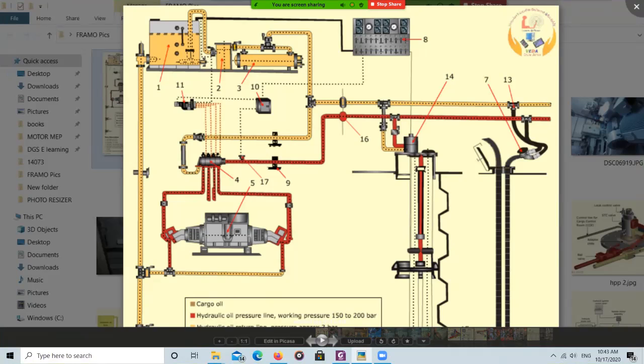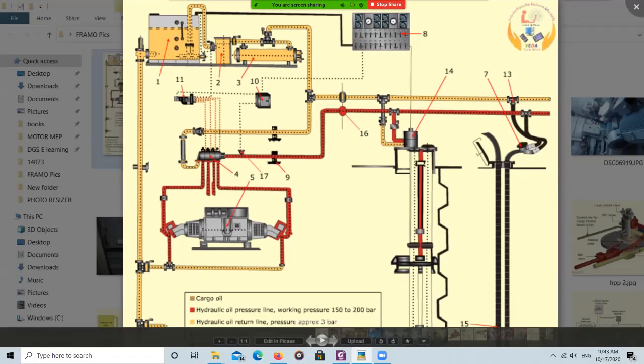The hydraulic system will not operate at full efficiency if air is inside. Contaminants may also enter which will damage and contaminate the hydraulic oil. Additionally, if the system is kept in positive pressure, any leak can be spotted directly — if there is a leak in the hydraulic line on deck or somewhere, the pump is running so you can identify the leak from that point.